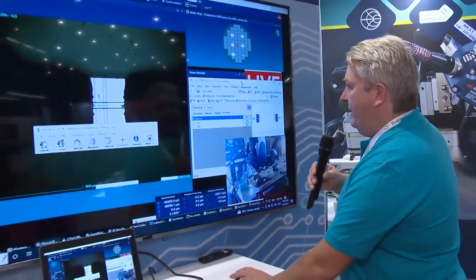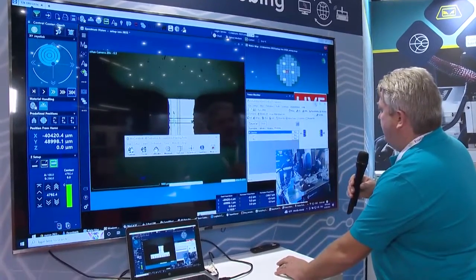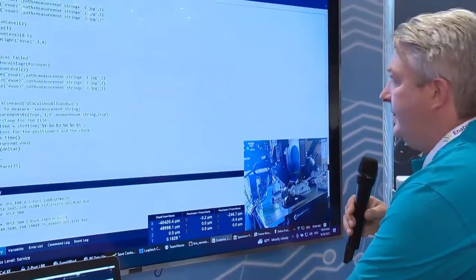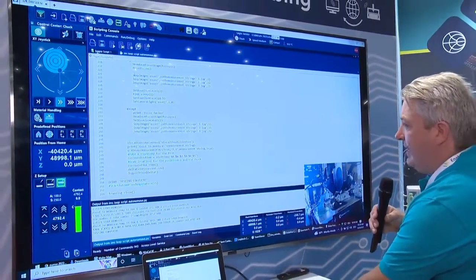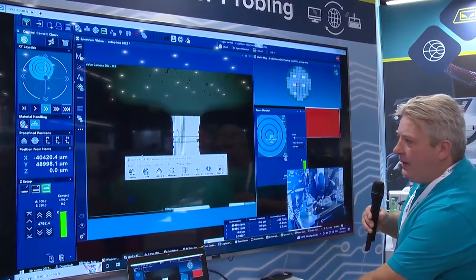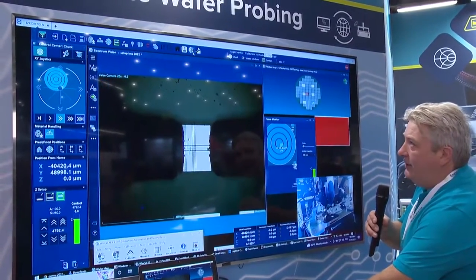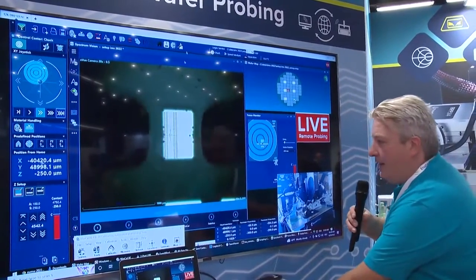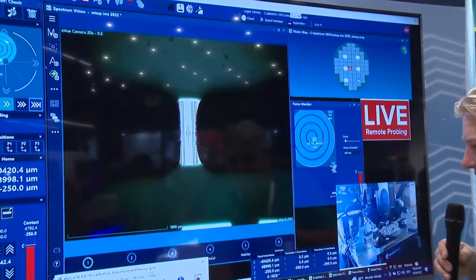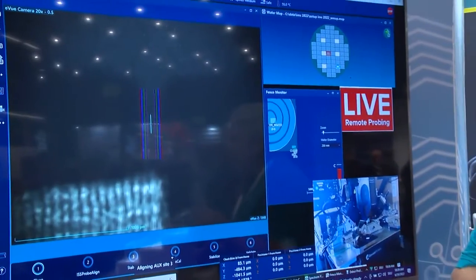Let me just minimize the screen for a moment. Right now you can see it's making a series of measurements. What's flashing here is our WinCal calibration software. Let me just stop this — stop our script. Testing is complete, so it actually finished its run. I want to get a calibration on my machine but I don't want to have to adjust the geometry — the geometry is spaced out here. So what I can do is just press this button and the system will now run through a calibration sequence. The first part of the calibration sequence is we want to clean the probes — make sure we haven't built up any contaminant that would otherwise affect the calibration. This happens over temperature, so we've got to be able to accurately find that cleaning media without any damage to our probes.